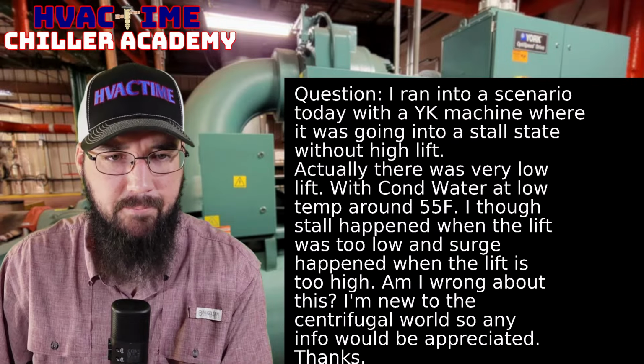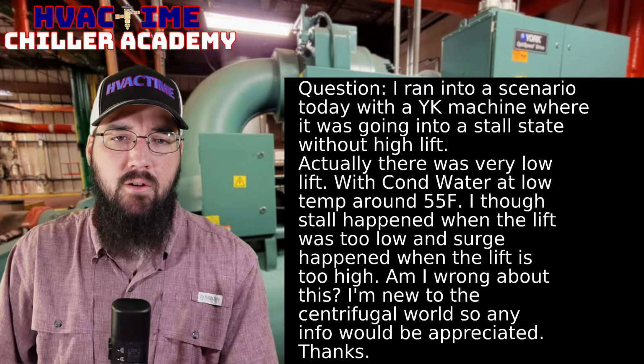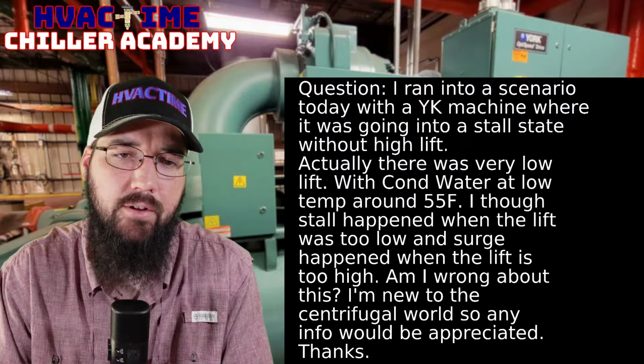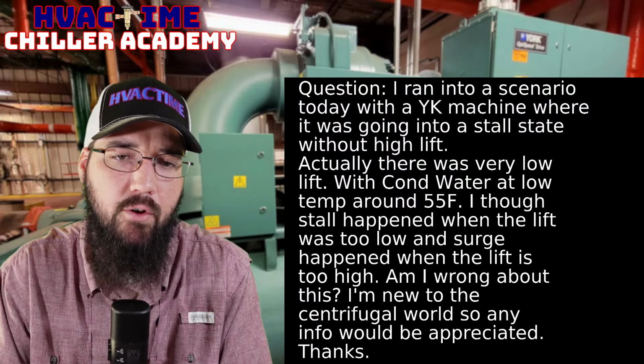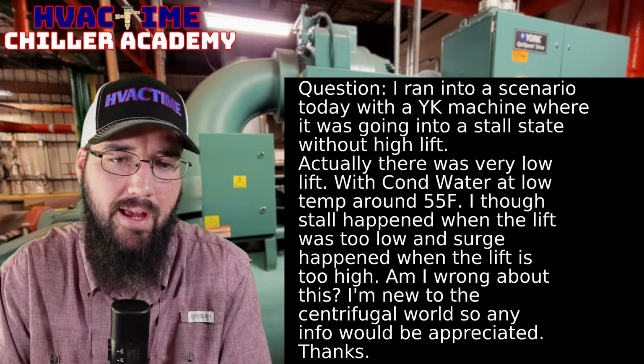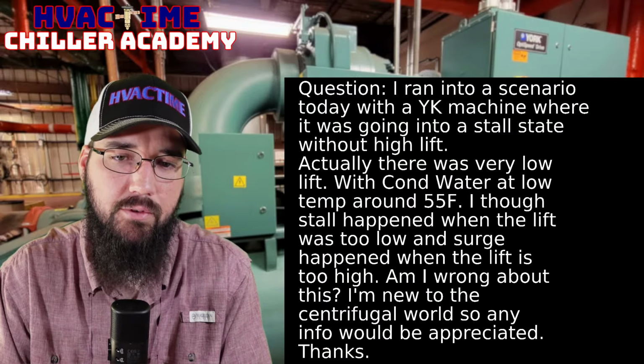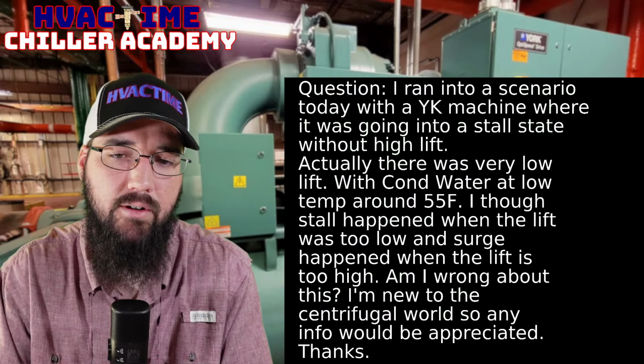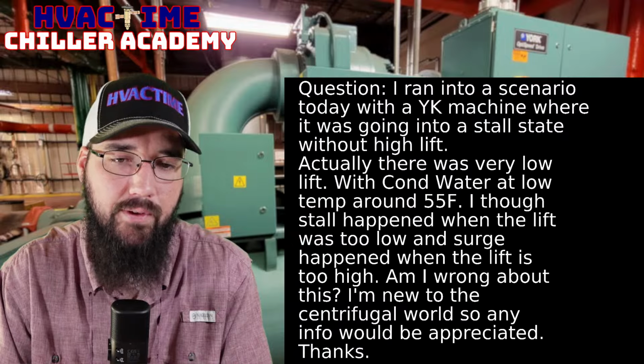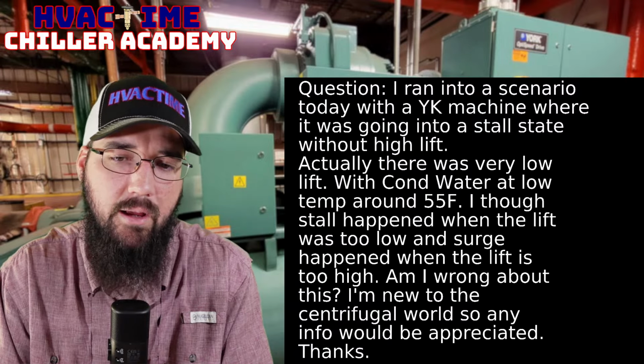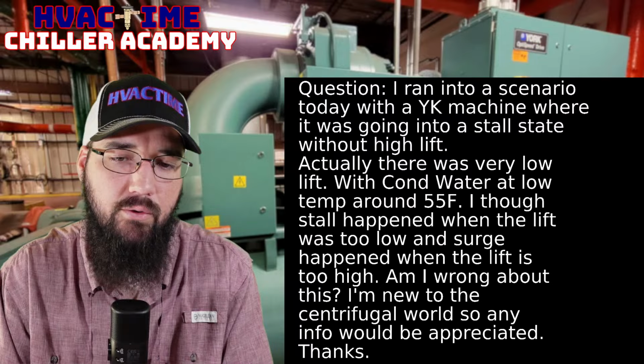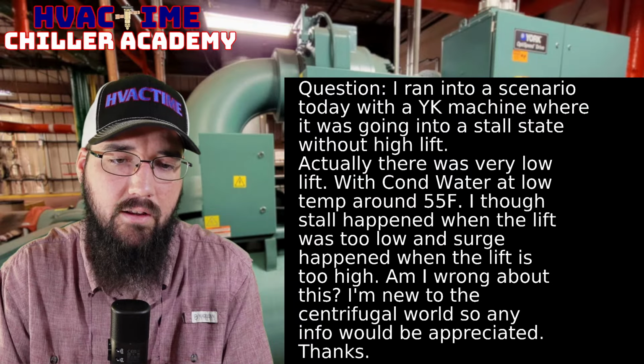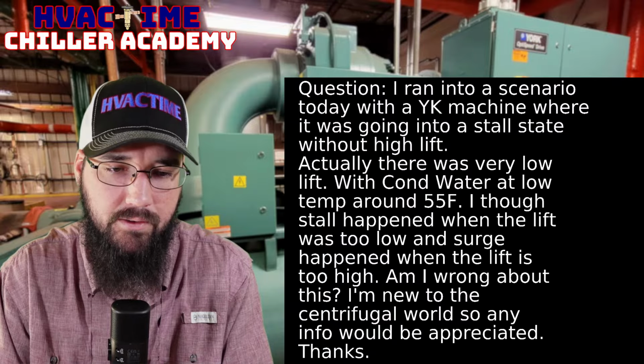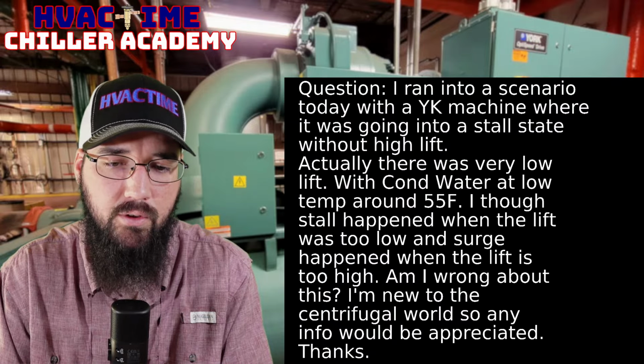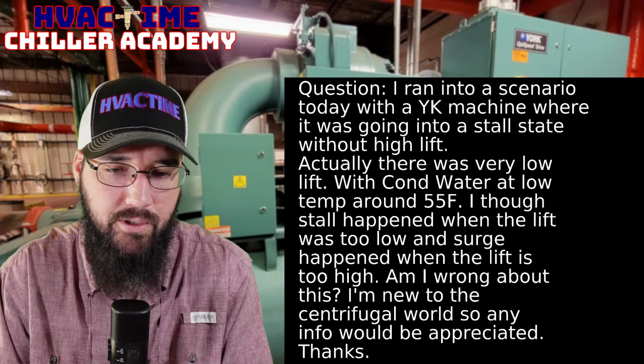This one is also about a YK. Question: I ran into a scenario today with a YK machine where it was going into a stall state without high lift. Actually, there was very low lift. The condenser water was at low temp, around 55 degrees Fahrenheit. I thought stall happened when the lift was too low, and surge happened when the lift is too high. Am I wrong about this? I am new to the centrifugal world, so any info would be appreciated.